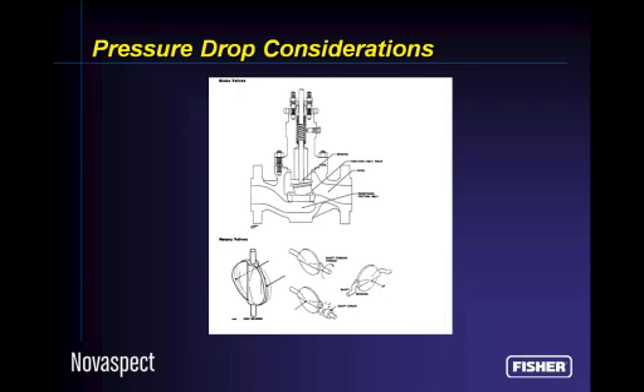Another very important attribute that needs to be considered for a control valve is the pressure drop across it. We're going to spend a lot more time talking about the pressure drop because the pressure drop across the valve is the parameter that most obviously determines how severe the service is for a valve. But even in the everyday general service valve, we need to consider the effect of the pressure drop across the valve on the internal components of the valve.